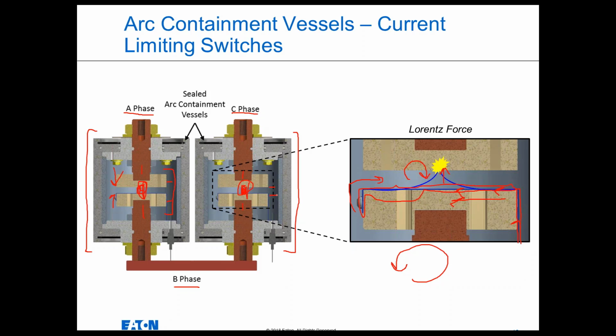So by containing the arcing fault inside these arc containment vessels and using special contact material that does not erode very quickly in the presence of an arcing fault, we ensure that the arc will not self-extinguish, that it'll continue to arc from A to B and B to C across these contacts, and it'll be fully contained. We won't let any of that energy escape into the environment and therefore potentially extinguish the arcing fault. So those two ways, we're sure that the arc quenching device will always be the path of lowest impedance when it's triggered by the arc detection relay.